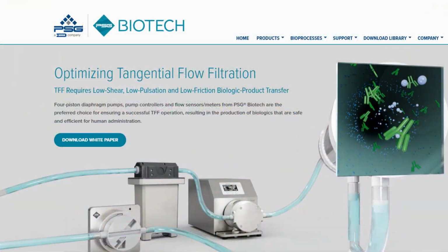Sure. And in TFF, for example, the fluid would change viscosity from start to finish, which could range from 1 to 40 centipoise in some cases. Correct. And some of these velocity meters can introduce errors anywhere from 20 to 40% in such scenarios. Whereas measuring flow by mass is inherently immune to those changes. So it's ideally suitable for applications in the biospace. Okay, and I think that's something we cover in my chemical engineering classes, just how to look at mass flow versus volumetric flow, and that is really the advantage of these Coriolis meters.